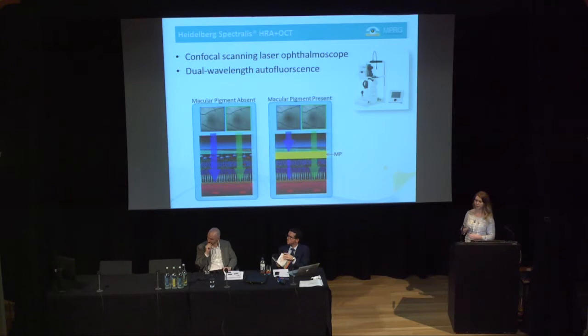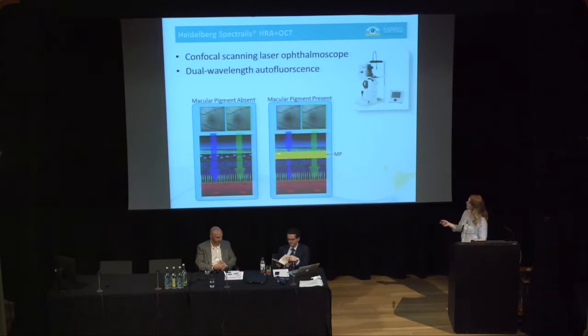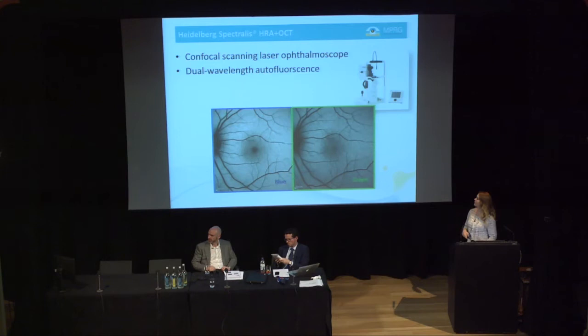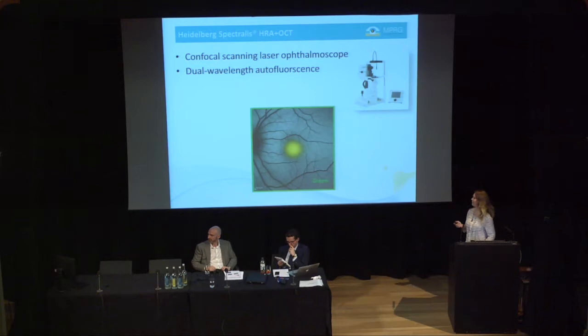The device we use in our lab for autofluorescence is the Heidelberg Spectralis HRA+OCT, a confocal scanning laser ophthalmoscope using dual wavelength autofluorescence. It takes two images simultaneously — we take a 30-second video of about 300 images in both a blue and a green wavelength. You can see that with macular pigment, the blue light is attenuated whereas the green is not. It aligns and averages all 300 images, and you can see this dark spot in the middle where the macular pigment is located. You then subtract the two images to get the amount of macular pigment.